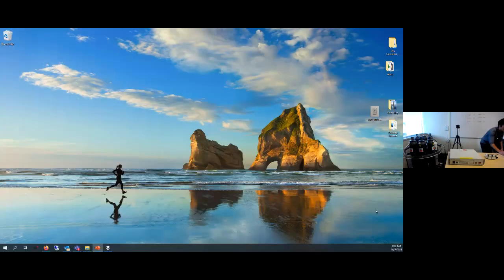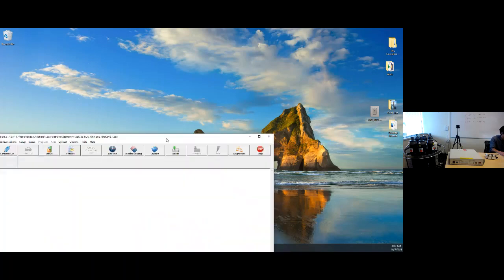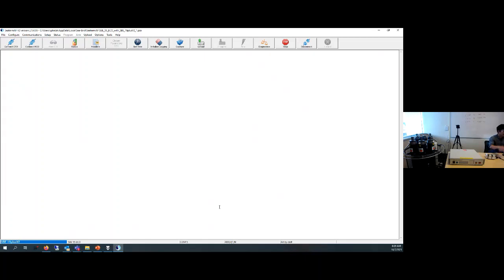Now I would like to get into some demonstrations of the software. The software that we're going to use with this system is called SeatermAF V2. This is very similar to standard Seaterm with some added tools for configuring and setting up your SBE 55 water sampler. This software also works with the AFM, the auto fire module that's used with the SBE 32, and gives us a lot of options here.